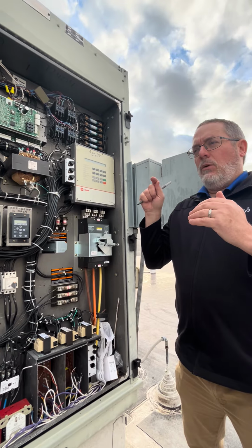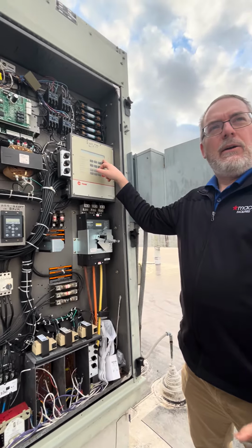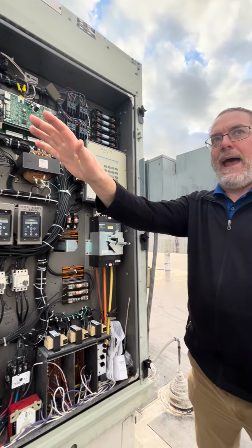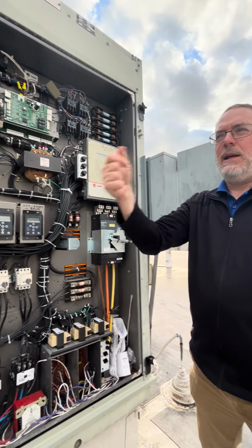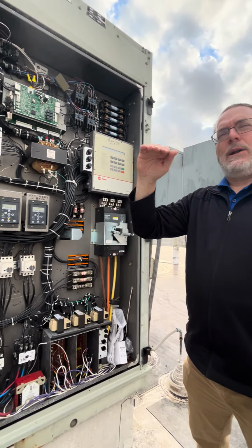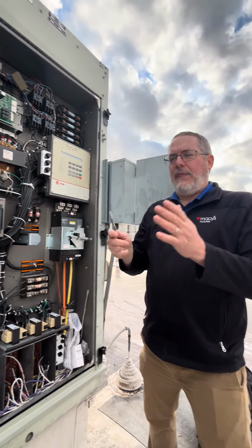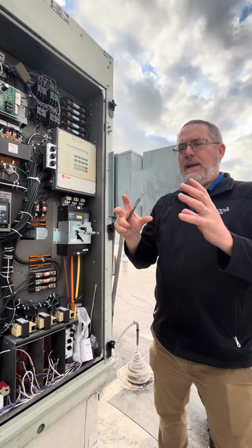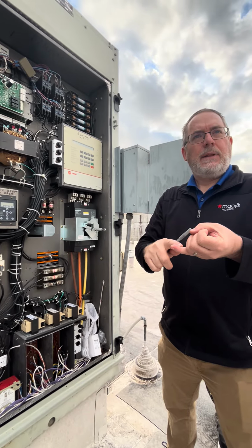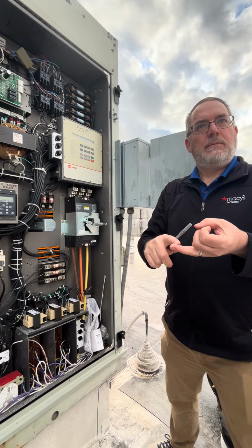Now, when you bring on this unit and you give me 50 degree air, and I've got that VFD humping at whatever I want to call max, maybe 90%. 80% on the VFD curve is kind of where we try to limit, because at that 80% on the VFD, you're delivering 80% of the CFM design, but it only costs you 50% of the motor horsepower.